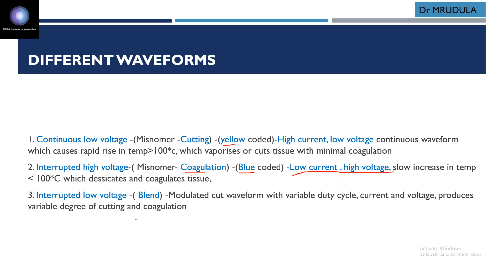While blend is a blending of these two. So it is an interrupted low voltage modulated cut waveform with variable duty cycle. As I told you, for fulguration they use a 6% duty cycle. That means 6% is active time. So it depends upon the percentage of active time. It is called a variable duty cycle. Current and voltage produce a variable degree of cutting and coagulation. It is known as a blend current, which is most commonly used actually.